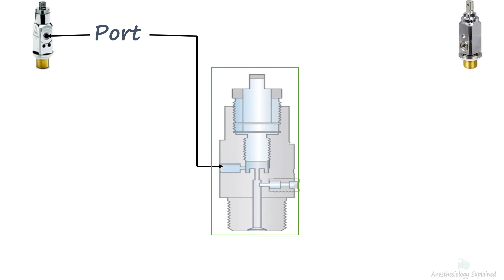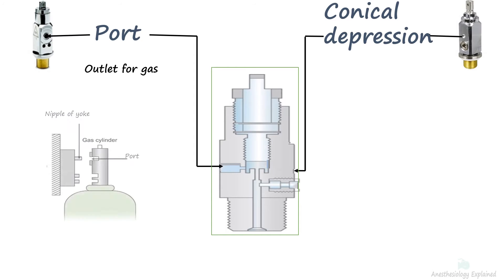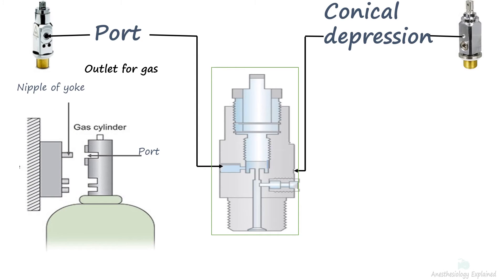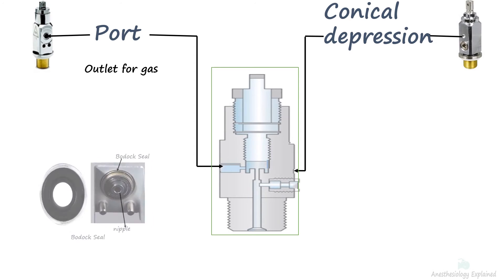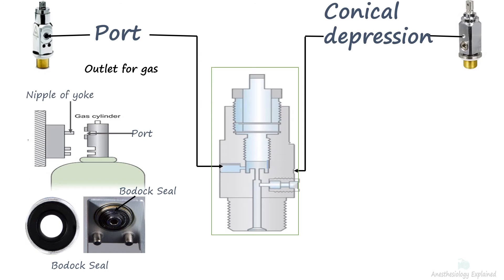The port and the conical depression lie on opposite surfaces of each other. The port serves as an outlet for gas and fits into the nipple of the hanger yoke in the anesthesia machine. It is covered by a seal or washer called a Bodock seal to achieve a tight fit with the nipple.